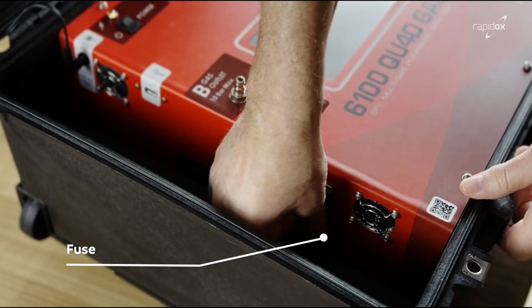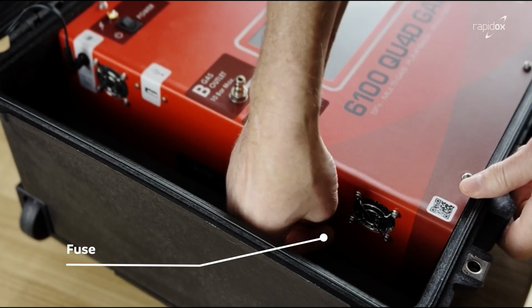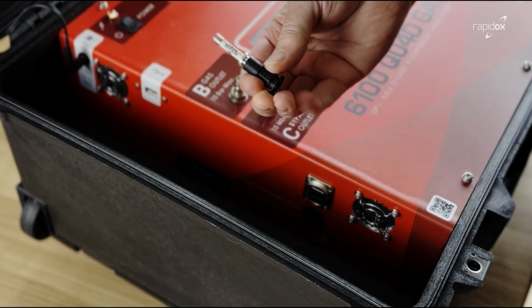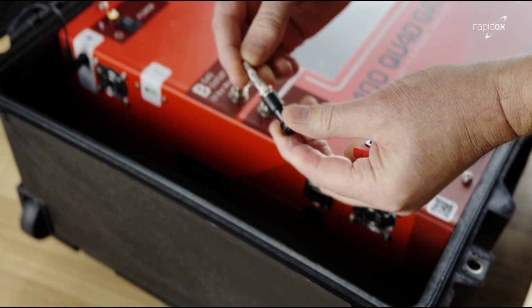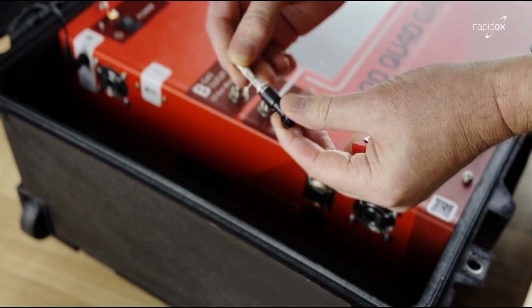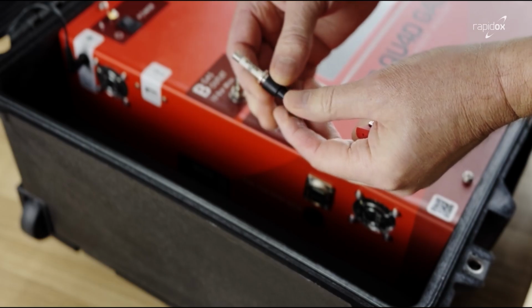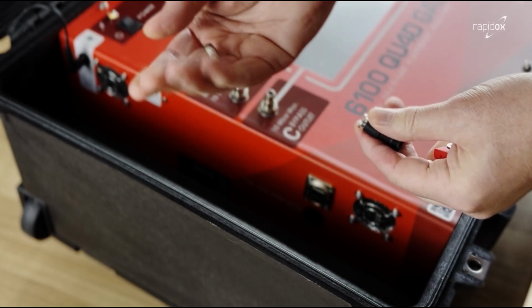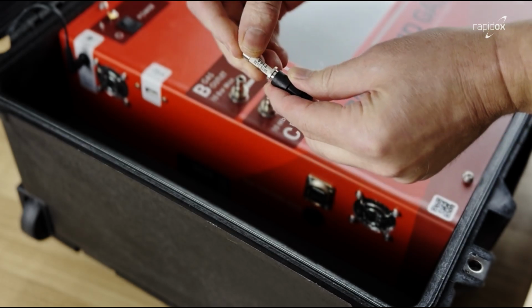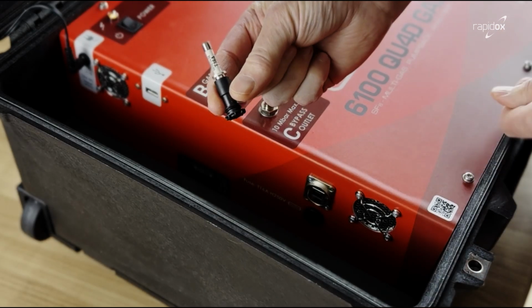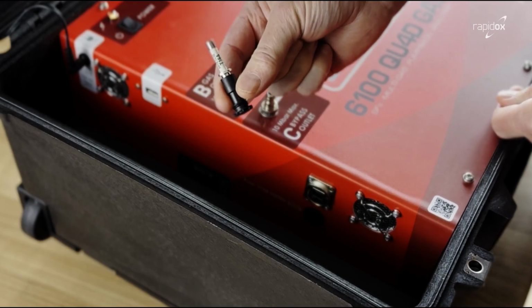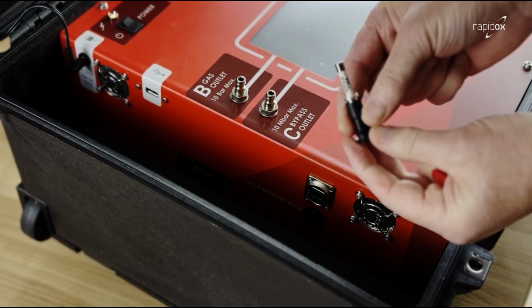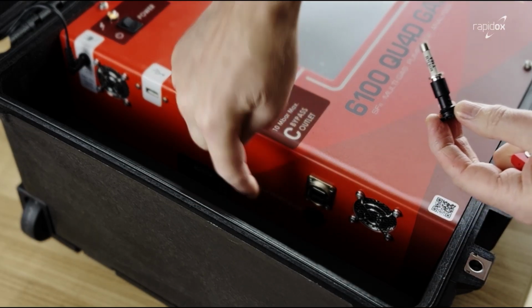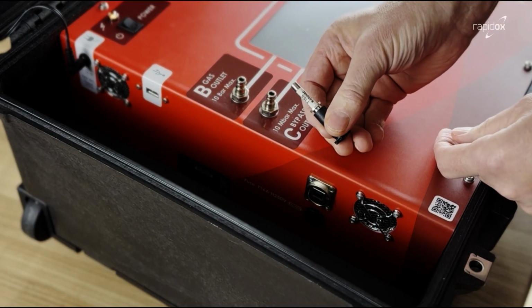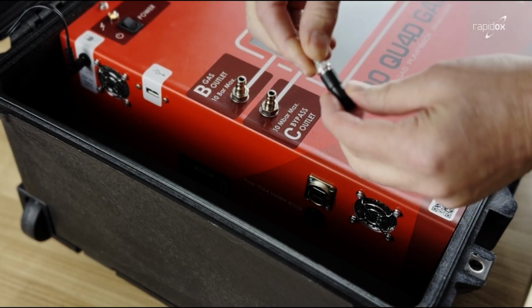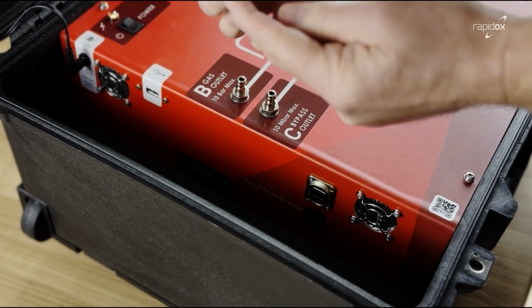Most importantly, down here is a fuse. And the fuse is here, and it is a T16 amp fuse, and it's very important that if the fuse has a problem and needs to be replaced, that it is replaced with exactly the same fuse. I believe the T stands for anti-surge, and it's very important that it's a T-rated fuse. On the actual artwork itself, which might be quite difficult to see, the correct fuse to use is printed.